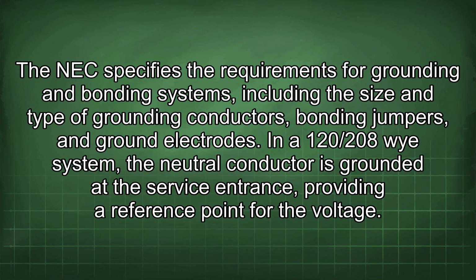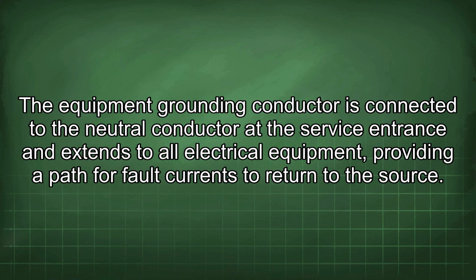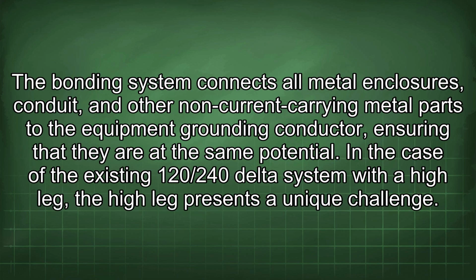In a 120/208Y system, the neutral conductor is grounded at the service entrance, providing a reference point for the voltage. The equipment grounding conductor is connected to the neutral conductor at the service entrance and extends to all electrical equipment, providing a path for fault currents to return to the source. The bonding system connects all metal enclosures, conduit, and other non-current carrying metal parts to the equipment grounding conductor, ensuring that they are at the same potential.